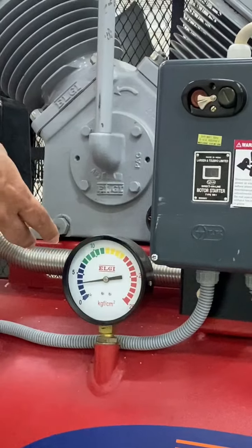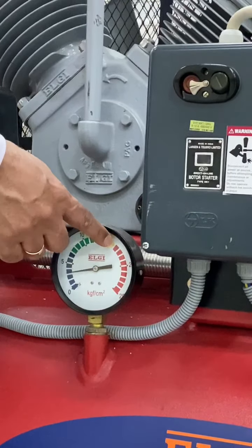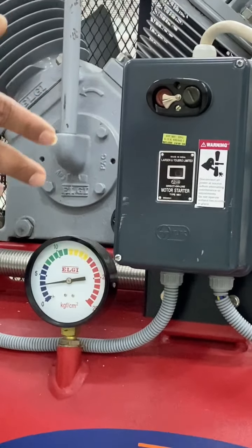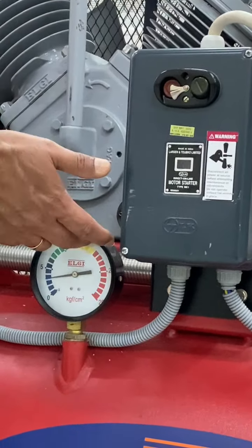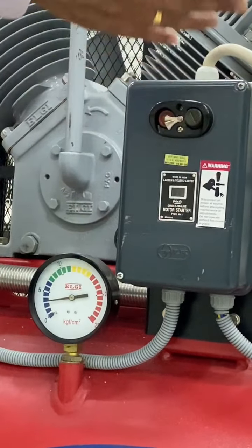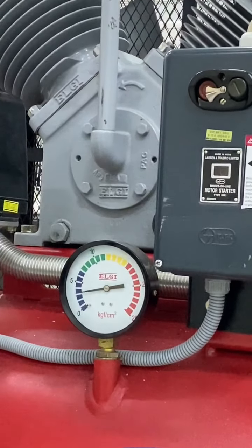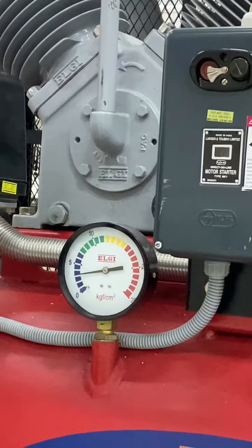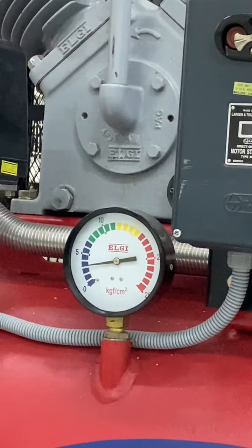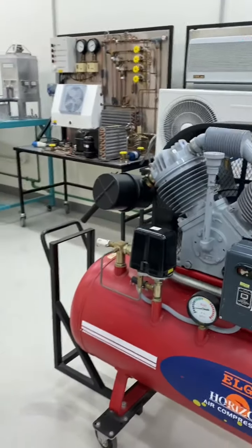So we have to wait for maybe 10 minutes to see whether at 12 kg per cm square the machine automatically stops. We need at least 10 to 15 minutes to reach that level, so that automatically it will stop. And if you release the air, again at 9 kg force per cm square, it will start automatically. The first one is cut off pressure, the other one is cut in. Two pressures are there. And 19.8 is the test pressure, giving enough factor of safety.